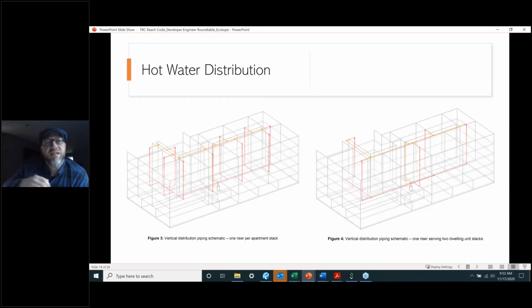Next important piece is the hot water distribution system. These are 24/7 loads, and you get one shot to insulate and design them properly. There's a lot of strategies right now on how to reduce the losses, but at the end of the day it comes down to your piping surface area and the insulation value around it. This is commonly referred to as the UA—the U value times that surface area. The UA of your piping system really represents the heat loss you will encounter.